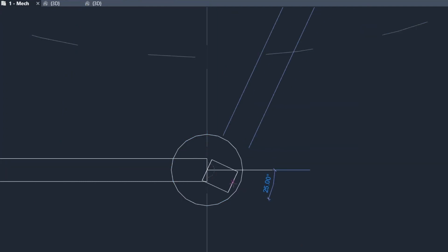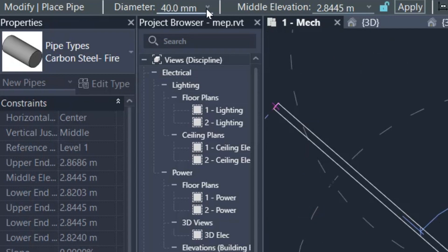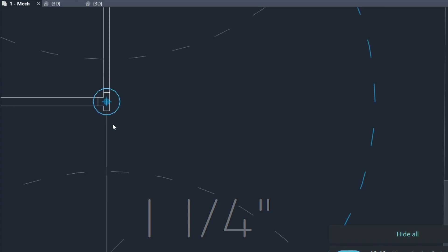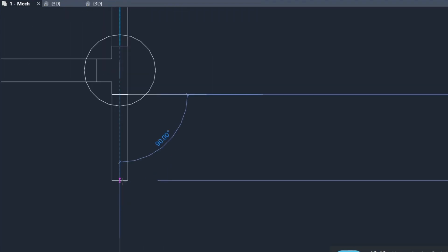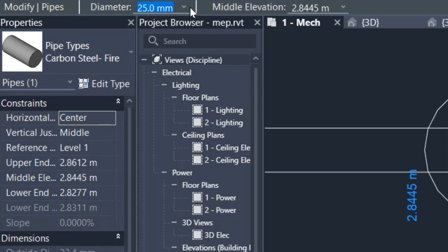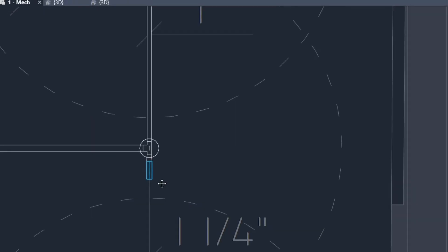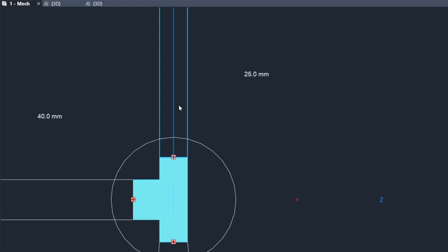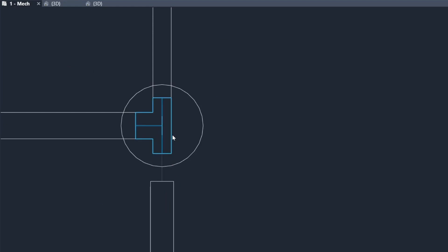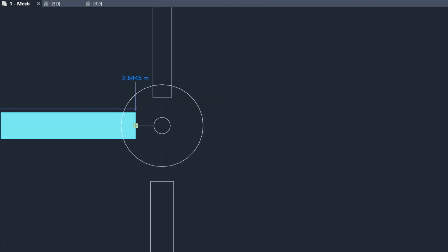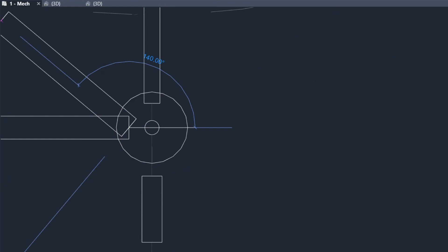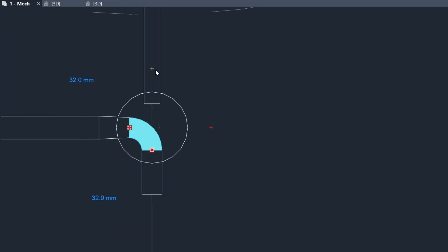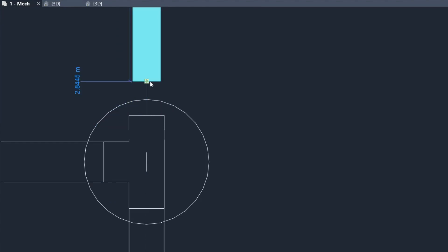For this branch, I'll use 25mm and bring it across. For the other side, use 30mm. Create the pipe, then select it and change the size to 32mm. You'll see a transition is created. If you want the junction to be larger rather than reduced there, delete the transition, right-click and draw a 32mm pipe to align it, then use the plus sign to connect them the way you want.